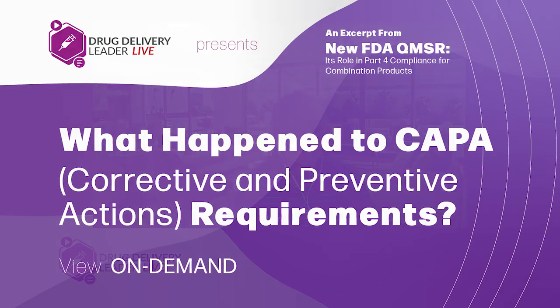Do you want to cover CAPA a bit? I do. That's where I'm going here, Fran. Okay. So the first thing is there is no CAPA. Okay? CAPA has gone away because 13485 has changed the terminology.